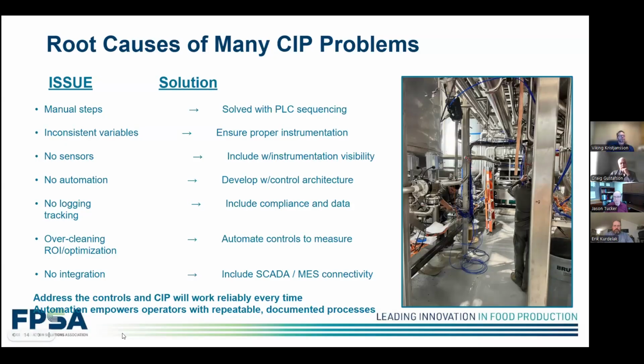Are there inconsistent variables? Do you have the right level of sensors, and how do they work? Do you have logging, and are you getting the logging you need to meet your BRC, SQF quality assurance requirements? Might you be over-cleaning so you're not getting the ROI you need - using too much time, energy, utilities, chemicals, etc.? And is it integrated so everything, including the SCADA, means your supervisors are seeing the same information as your operators? Typically, that's what your controls bring into the picture from a CIP perspective.